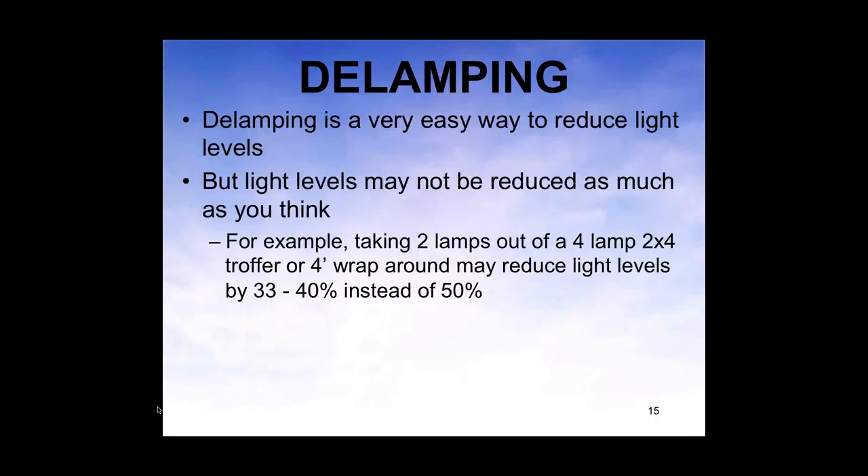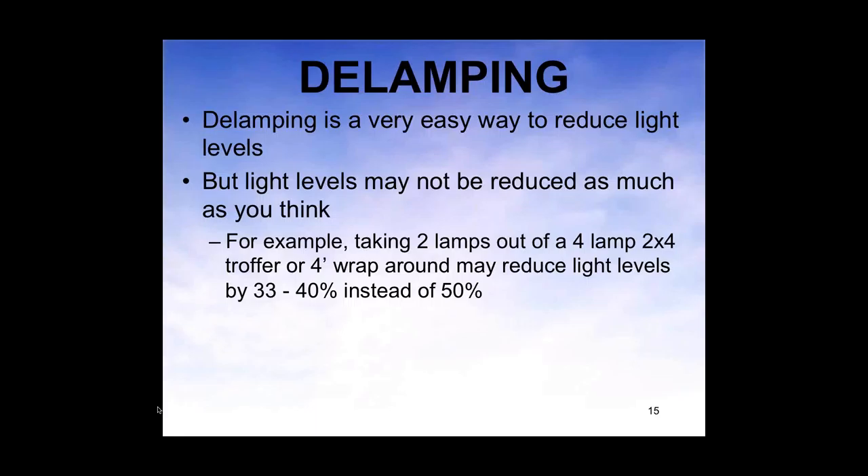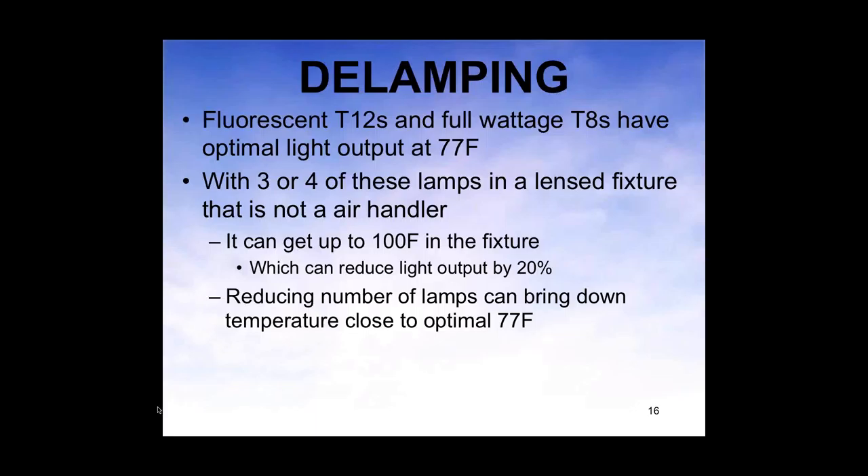A lot of people think more light is better — that is not always the case. The MDEQ can loan light meters, which can be a big help. Delamping is probably one of the easiest ways to reduce light levels. But sometimes you might not reduce the light levels as much as you think. For example, if you go from 4 lamps to 2 in a 2x4 troffer, you might only lose a third of the light, not half, and there are some reasons for that.